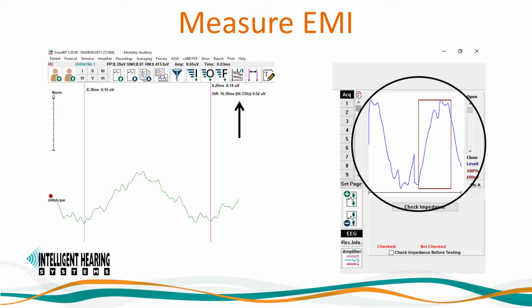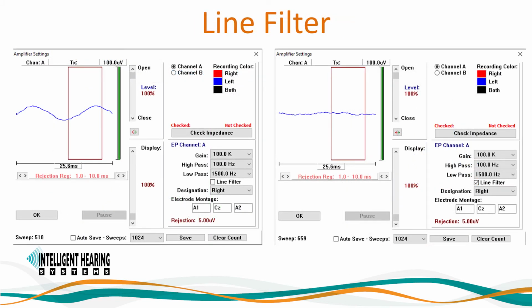You may need to modify your display time region to include the pre-stimulus. Use the cursor feature to measure and estimate the period of any waveform. The software will calculate its frequency in the difference indicator as shown in the parentheses. Note, myogenic activity from a patient will fluctuate. Link the frequency of interference to its likely origin. Some countries' power line noise will have a period of 16.5 milliseconds, or 60 Hz, and others will have a period of 20 milliseconds, or 50 Hz.